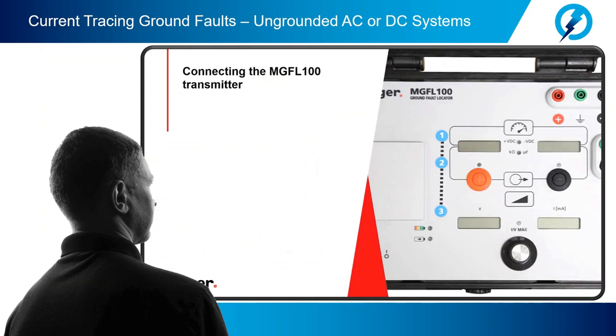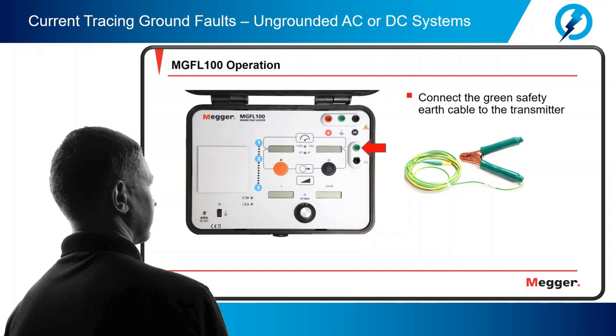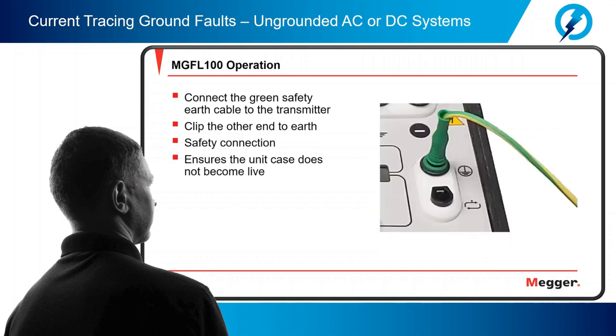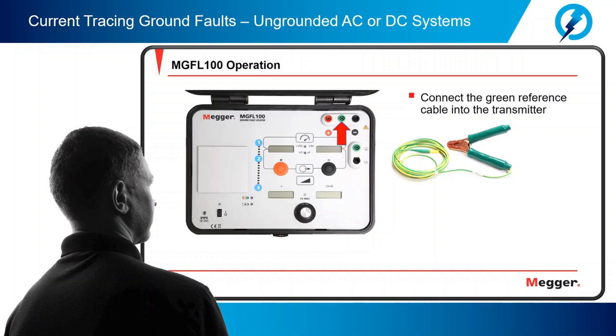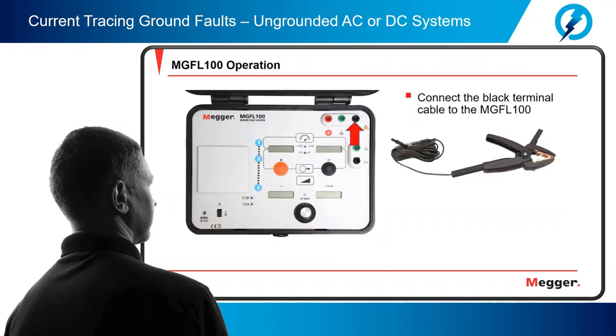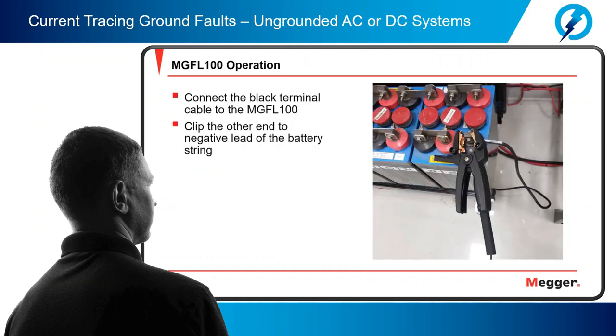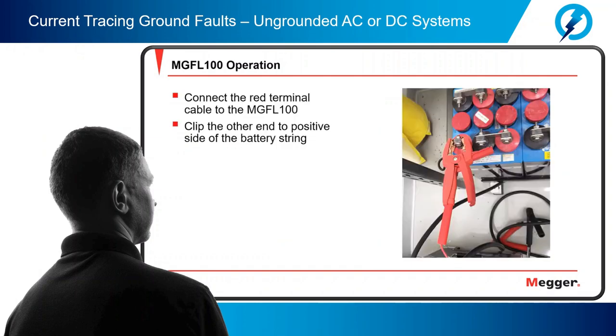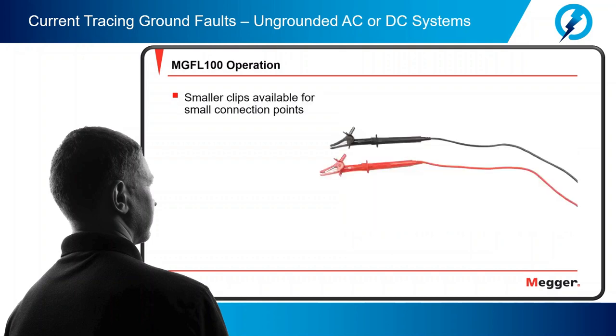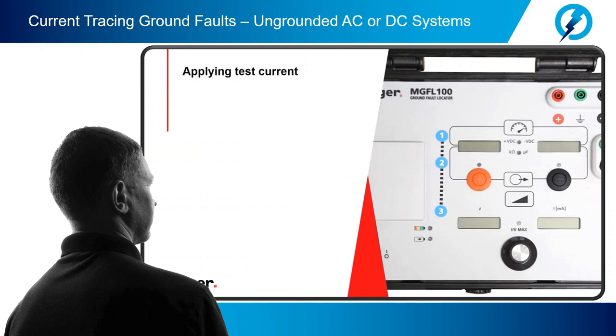Now we are ready to connect the MGFL-100. First, plug the green safety earth cable into the transmitter and clip the other end to earth — a conduit is a good connection. This is a safety connection that ensures if anything fails in the unit, the case does not become live. Next, plug the green reference cable into the transmitter and clip the other end to earth. Plug the black terminal cable into the MGFL-100 and clip the other end to the negative lead of the battery string. Plug the red terminal cable into the MGFL-100 and clip the other end to the positive side of the battery string. The MGFL-100 can be used on battery strings up to 600 volts DC. There are also smaller clips available for small connection points. Now we are ready to apply test current and evaluate the fault.